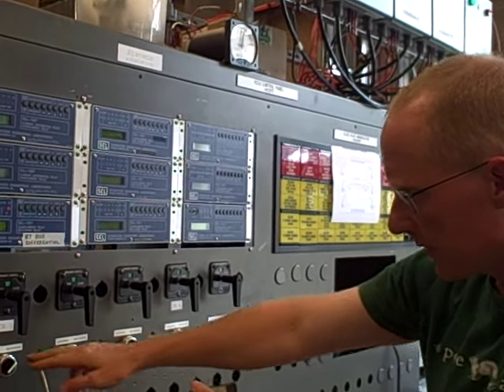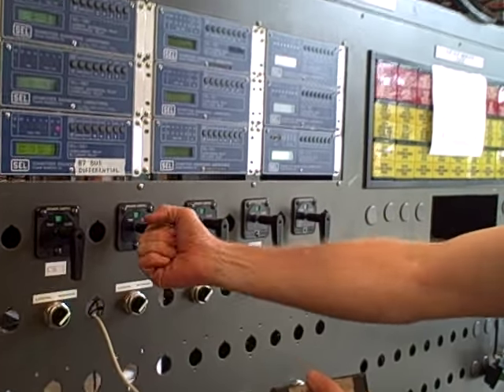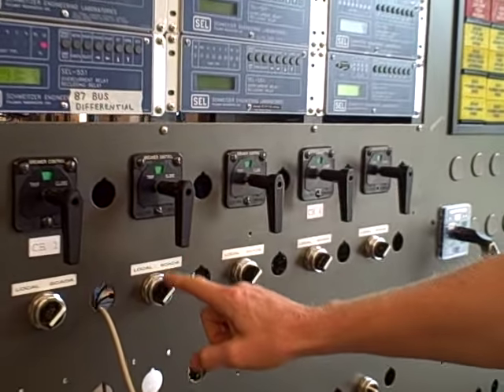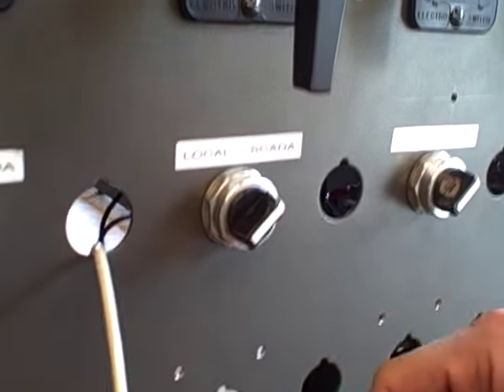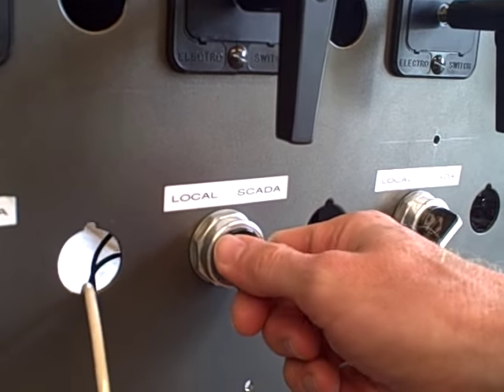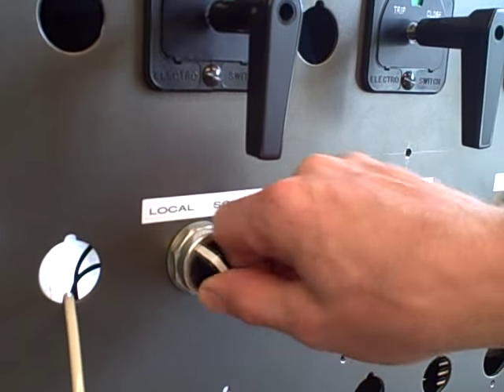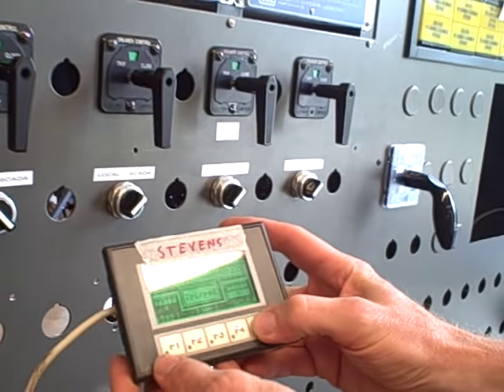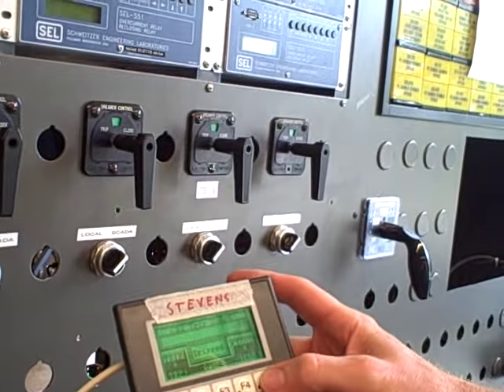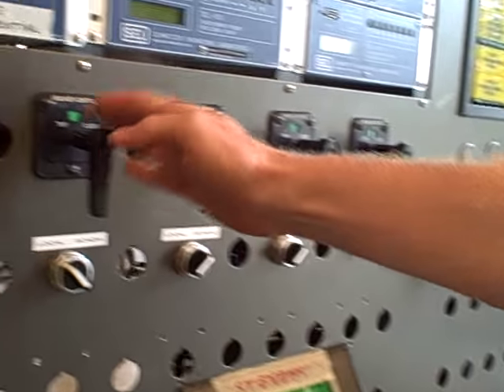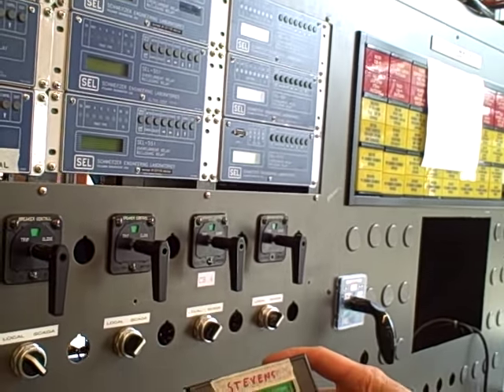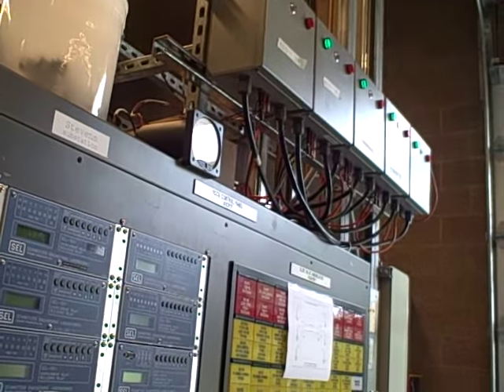You can see here every breaker control is manual, plus it has a local or SCADA selector. If I take it out of SCADA mode and go to local, now this does not work. Now I only have local control over the breaker. I cannot remotely close or trip it.